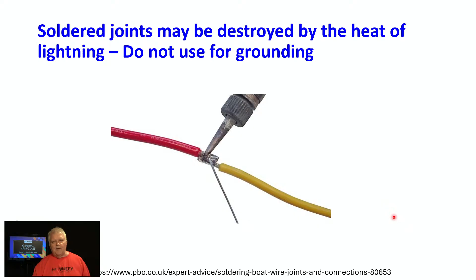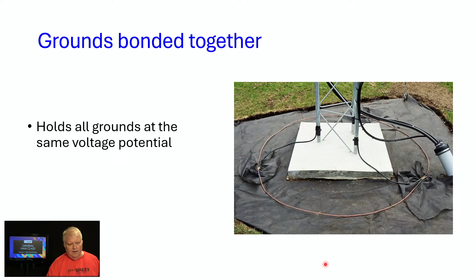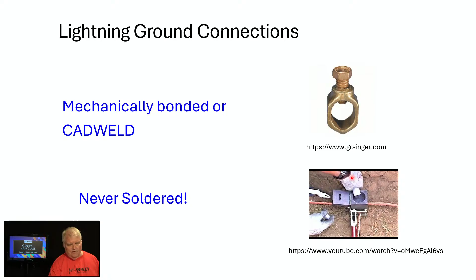Here we have a tower. Each of the tower legs is sent to a ground rod, an 8-foot ground rod driven into the ground. And then each of the ground rods is connected together as well with this circle of wiring here. That's the proper way to connect up grounds together. And then, as I mentioned, mechanically bond them or CAD weld. This is a CAD weld system down here at the bottom, never soldered. Oh, and did I say, put these lightning arresters outside the ham shack.